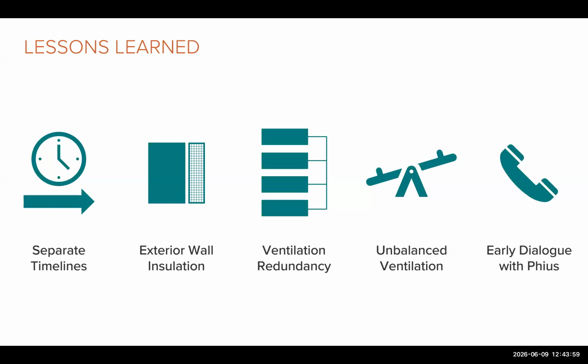The first big lesson relates to separate timelines. As you've seen, MEP coordination is critical, and we really needed to contract MEP for tenant fit out earlier in the process. The next one is exterior wall insulation. I think due to the separate timelines, the initial internal and process load estimates locked in envelope decisions pretty early on. So smaller heating demand confirmed in the later tenant fit out CD phase actually revealed we could have reduced the continuous exterior insulation slightly below 4 inches. So that was a good lesson there.